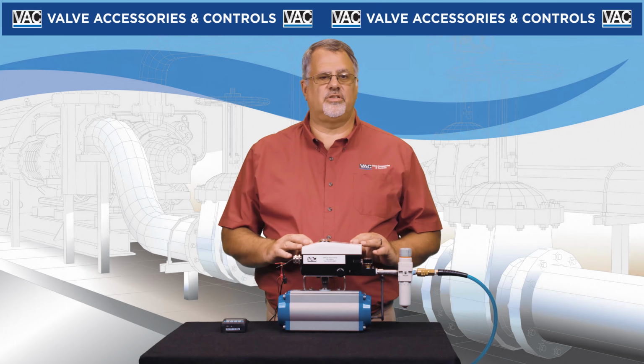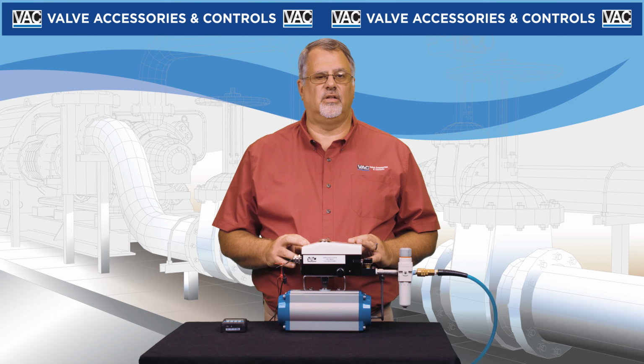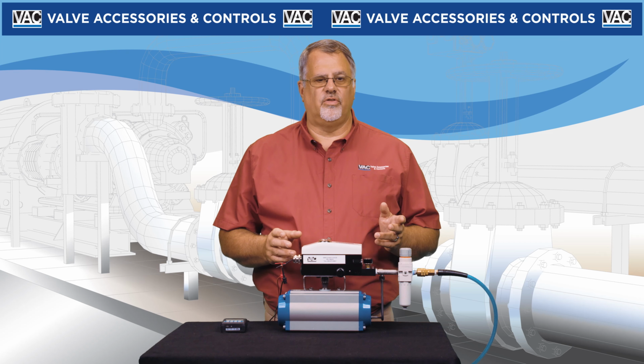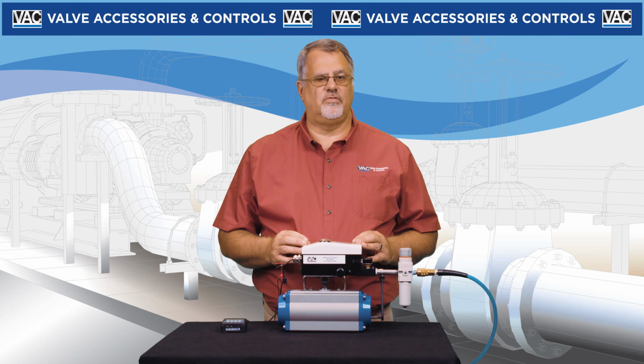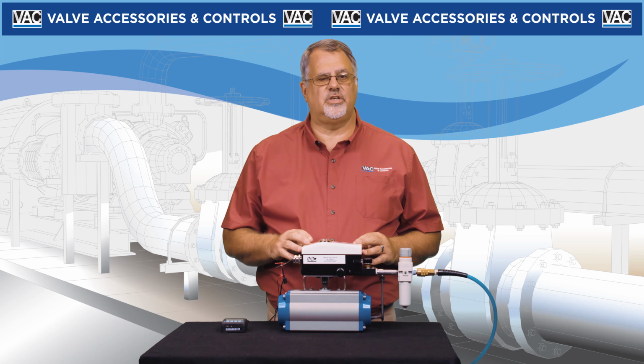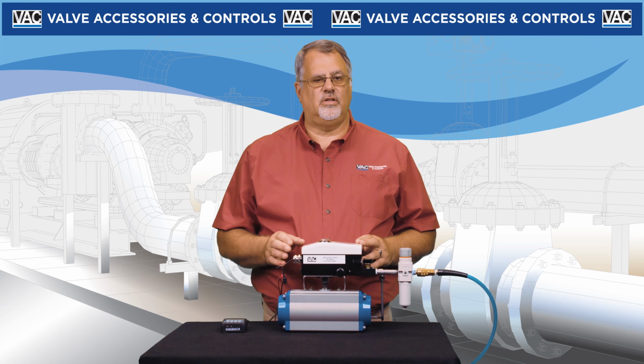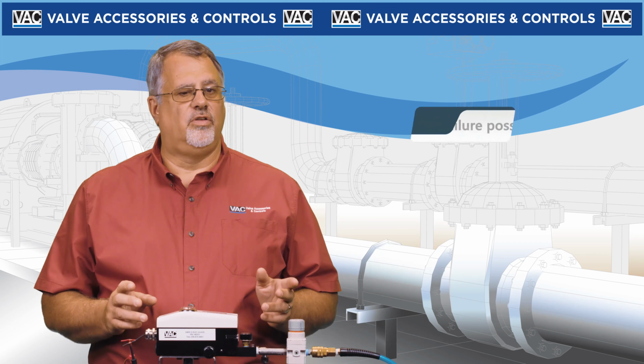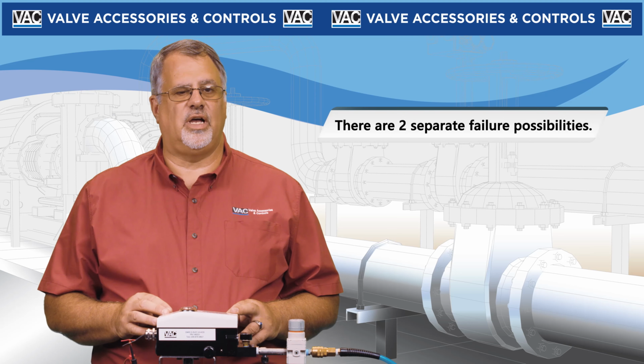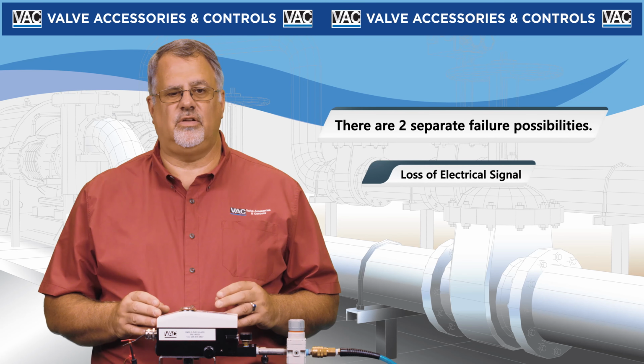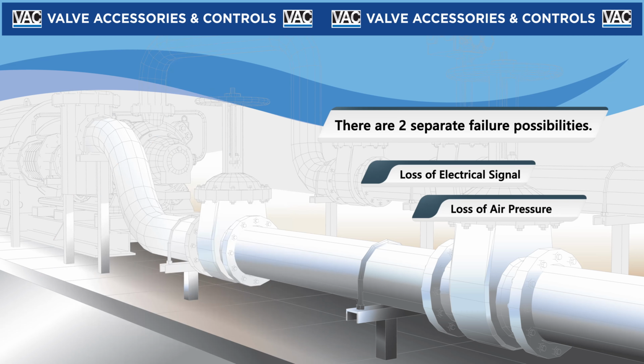Control valves with a positioner react differently to loss of signal or air pressure than solenoid-operated on-off valves do. When using a standard valve positioner, the normal behavior is for the positioner to drive the valve to the minimum signal position whenever electrical signal or air pressure is lost. Note there are two separate failure possibilities: loss of electrical signal or loss of air pressure.